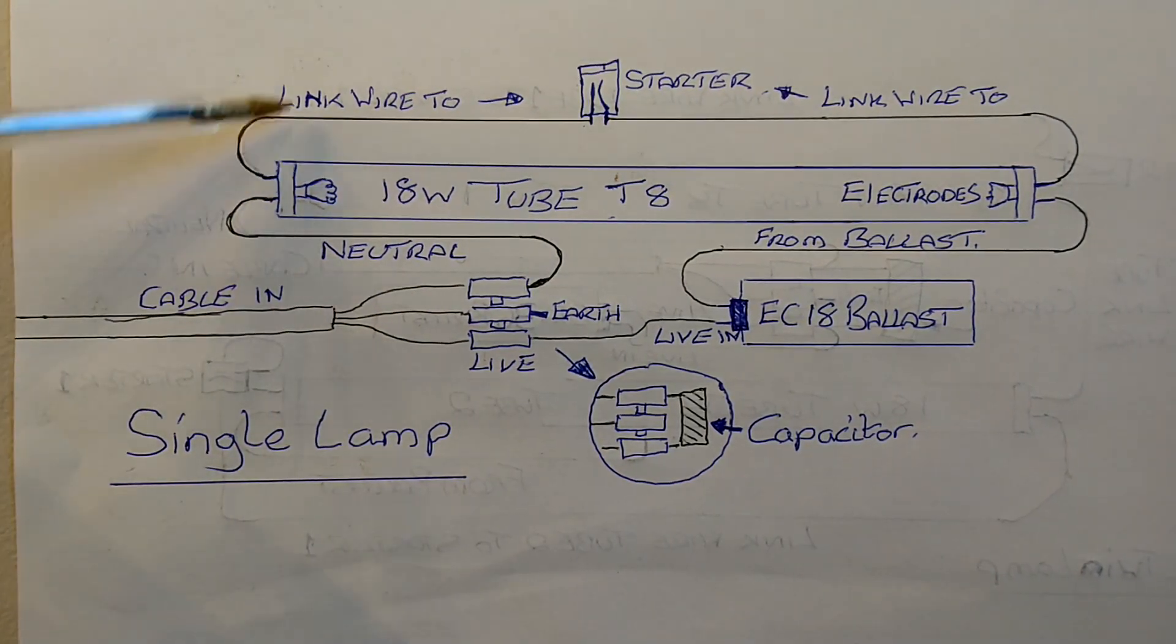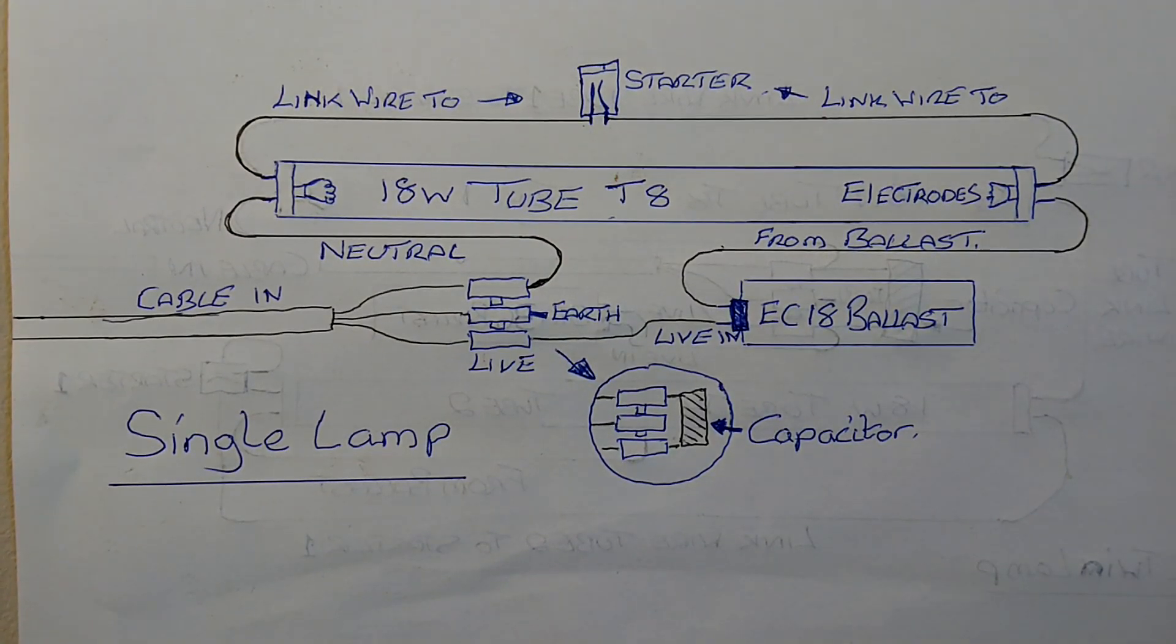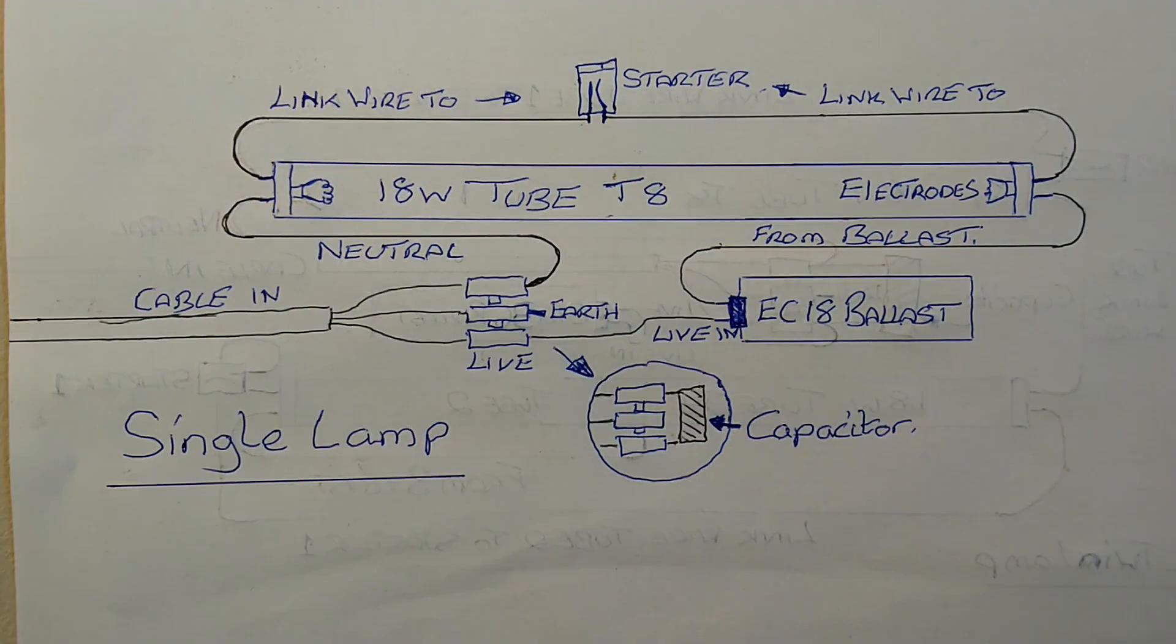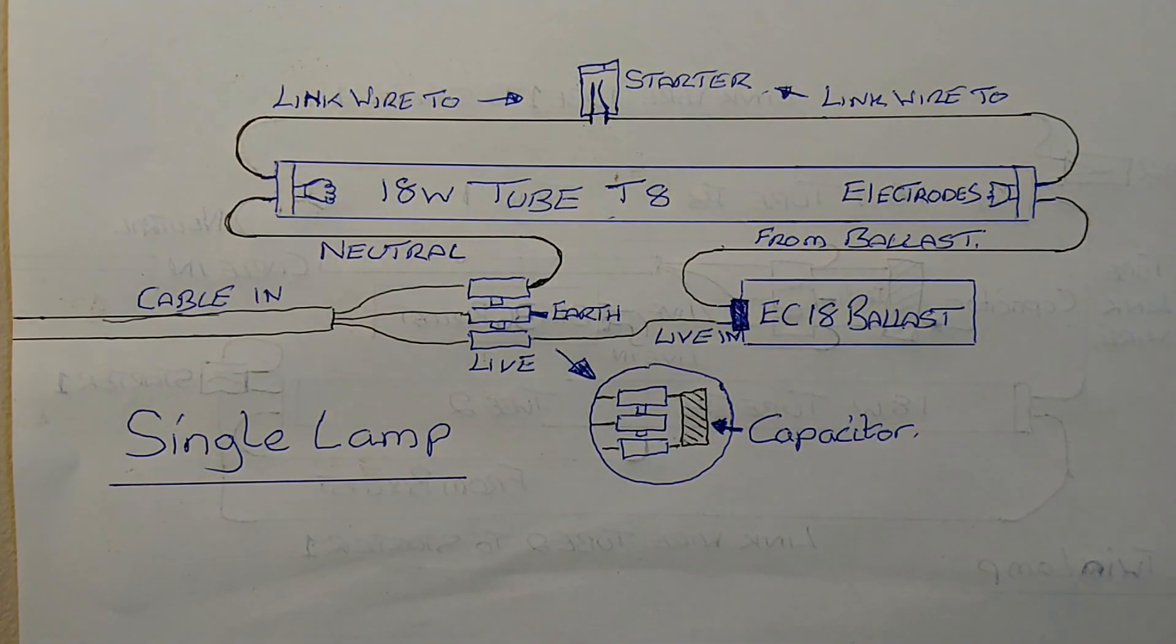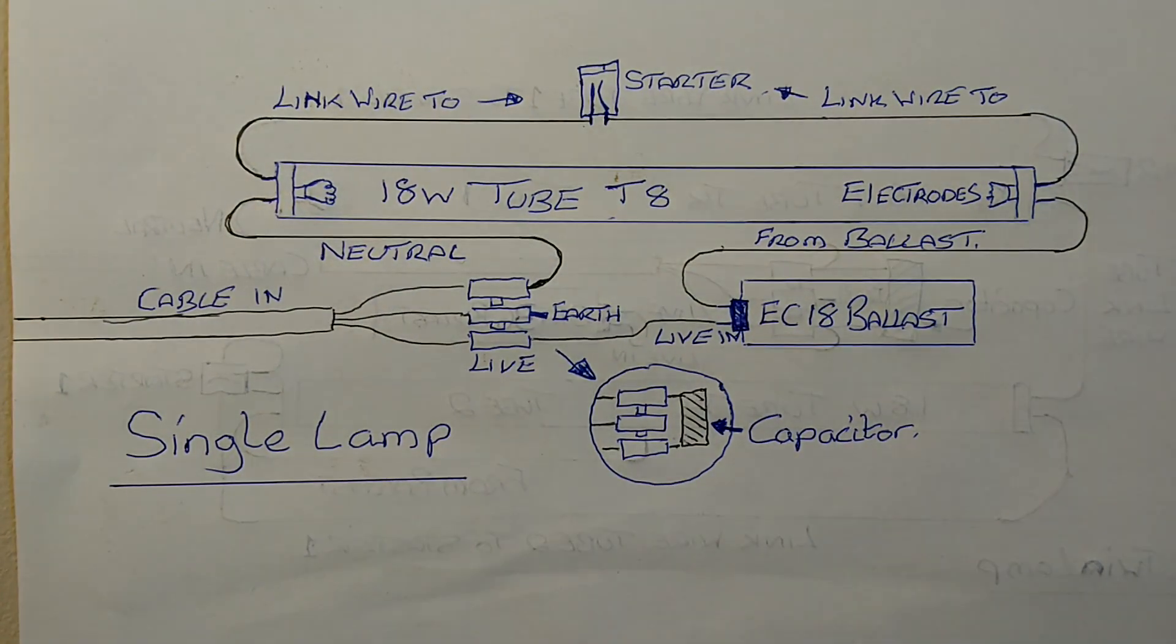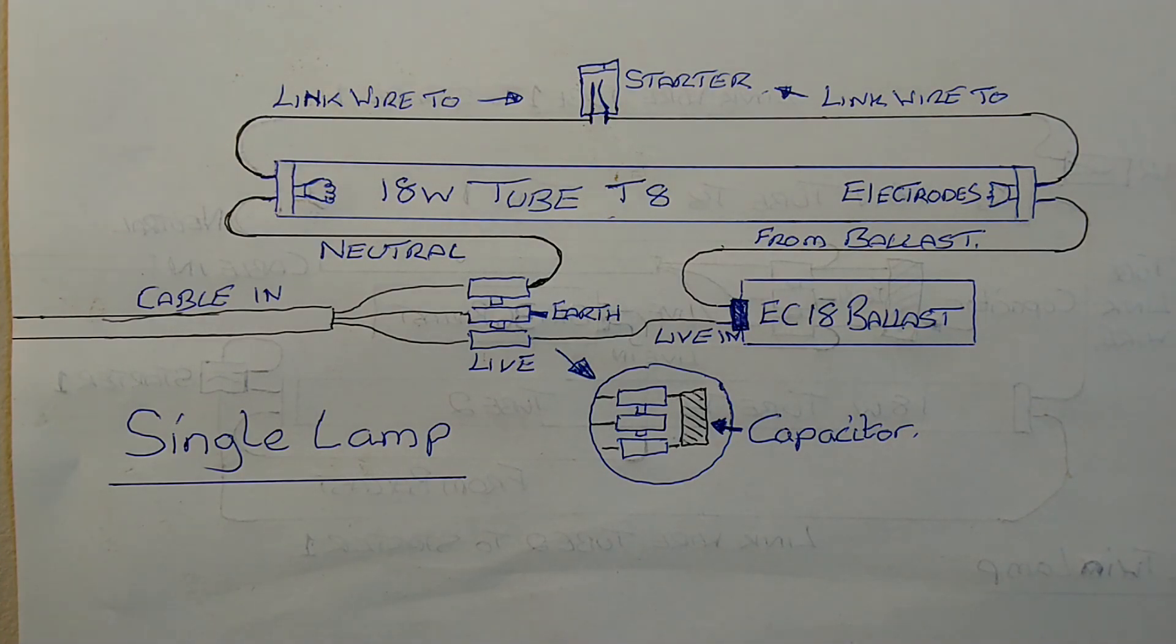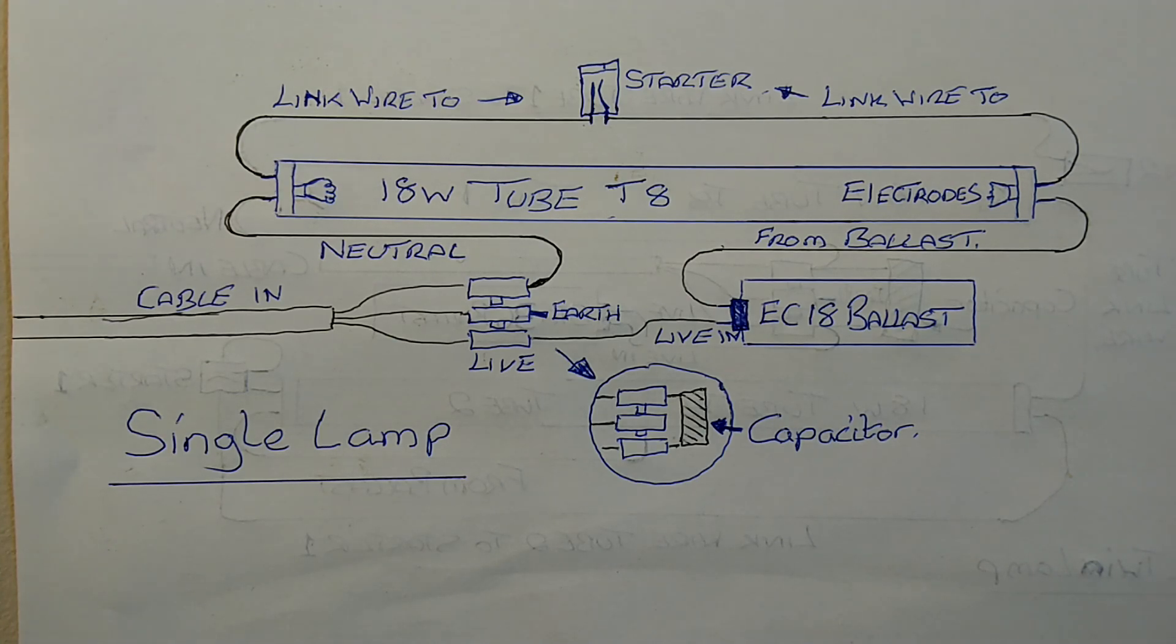And then the starter is connected between the tube on either side. When power is connected to the ballast, power runs through the starter and it touches, and then both electrodes fire. And then the starter, if working correctly, separates and the tube works. Sometimes this may take one or two attempts.